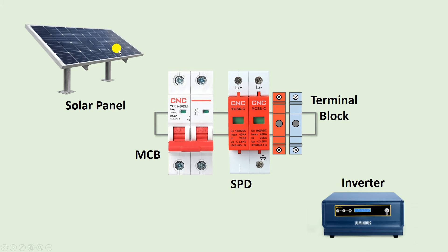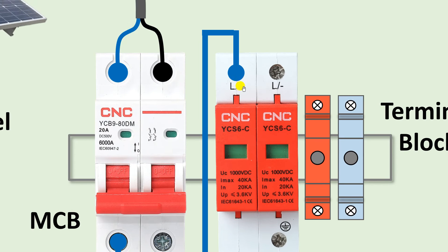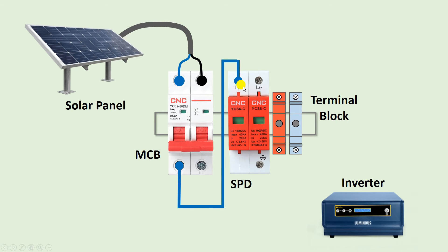For connection of this distribution box, the power supply coming from the solar panel — first of all connect this with the MCB. Connect the positive power supply to the positive terminal of the MCB. From that point, connect a wire to the positive terminal of the SPD — you can see the positive symbol there, so connect positive power supply at that terminal.